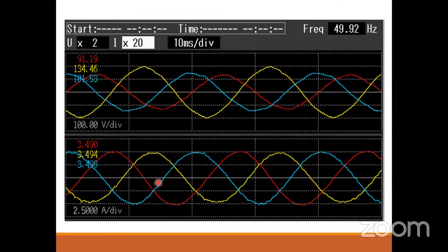What will happen if there is any disturbance on the grid side? For example, on your screen you can see the three-phase grid voltages, and this is an unbalanced grid voltage because of a fault in the grid. You can see three different voltages. The grid voltage is unbalanced, but the grid current is purely balanced. In the phasor diagrams, the grid voltage unbalance is 26.11%, but the grid current is balanced, and its unbalance is totally negligible, close to zero. This is the beauty of this controller. This type of controller also takes action during grid side disturbances.